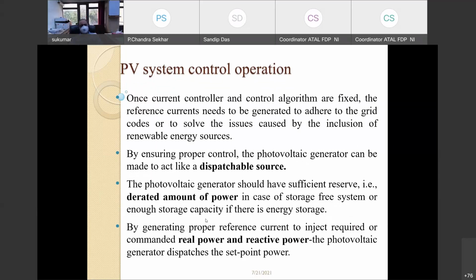Now, the multifunctional inverter can also be made a dispatchable source if we derate the photovoltaic and do not operate it in the MPPT mode, so that any power command can be given to the solar photovoltaic system, and the derated amount of power can be handled in such a way that it can provide dispatchable power to the grid, and both real and reactive power can be dispatched based on a set point provided by the grid operator.